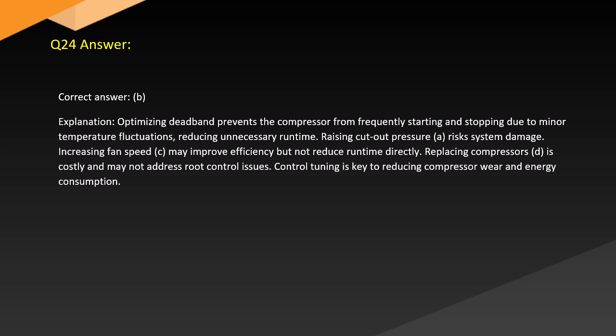Answer. Correct answer: B. Explanation: Optimizing deadband prevents the compressor from frequently starting and stopping due to minor temperature fluctuations, reducing unnecessary runtime. A, raising cutout pressure: risk of system damage. C, increasing fan speed: may improve efficiency but not reduce runtime directly. D, replacing compressors: is costly and may not address root control issues. Control tuning is key to reducing compressor wear and energy consumption.